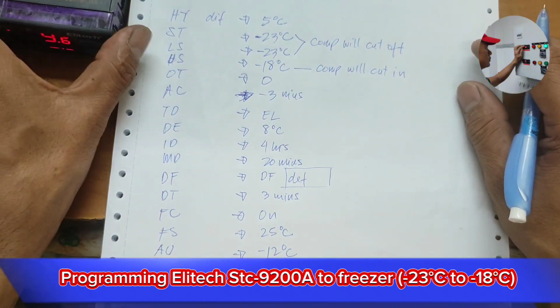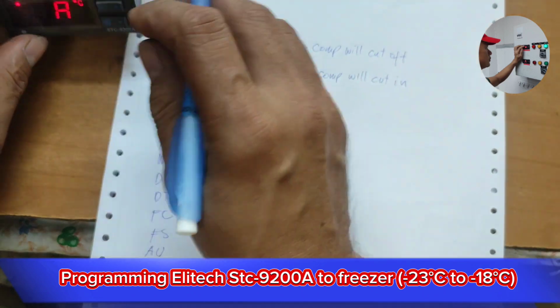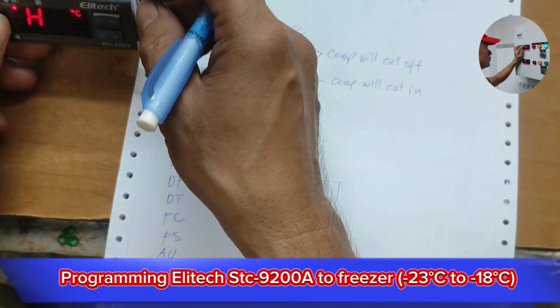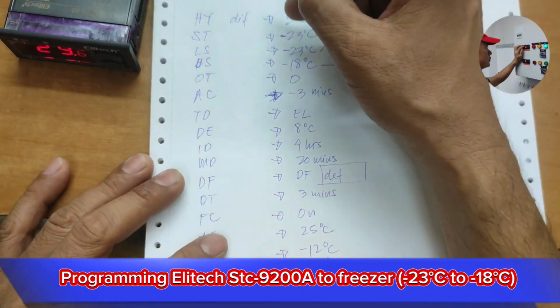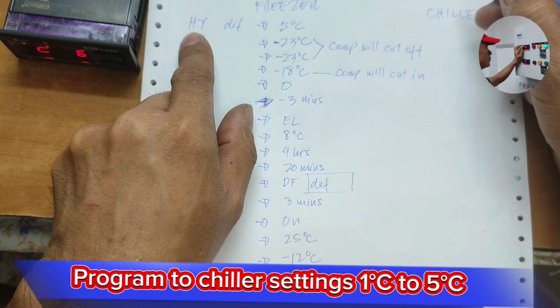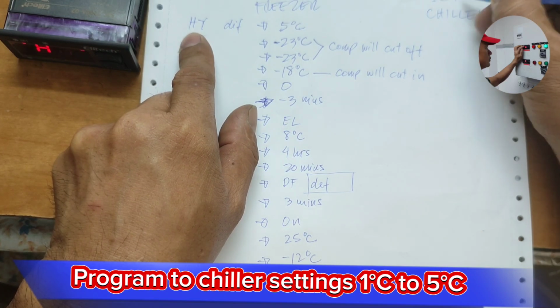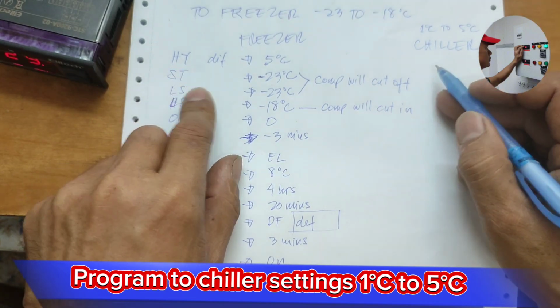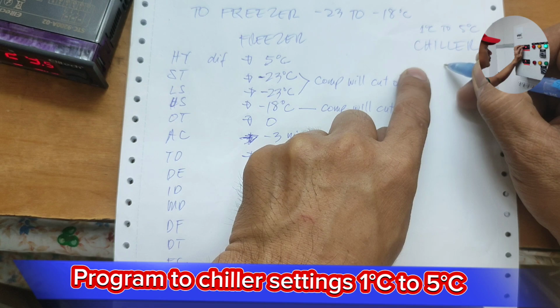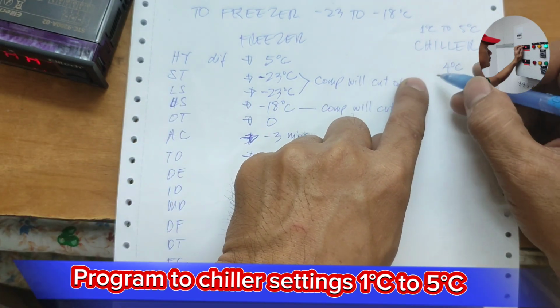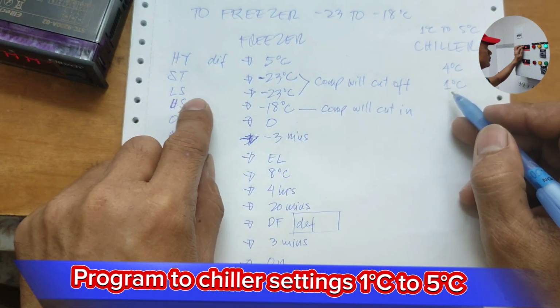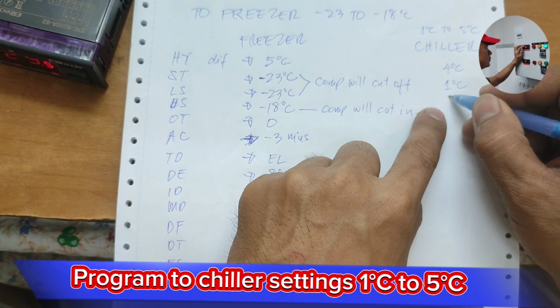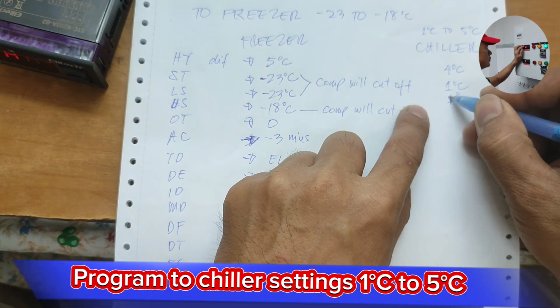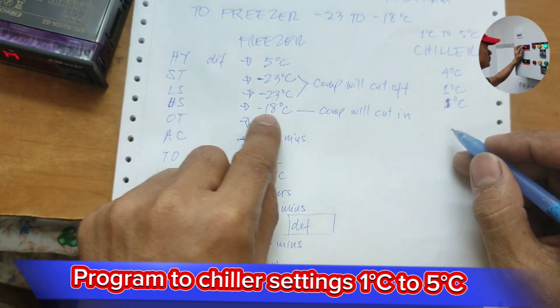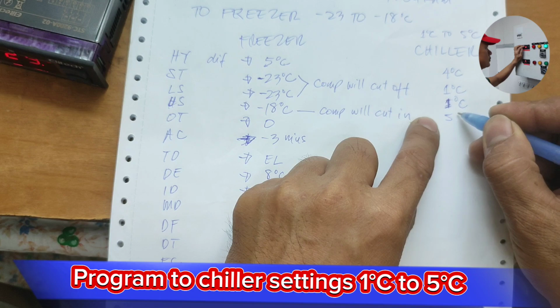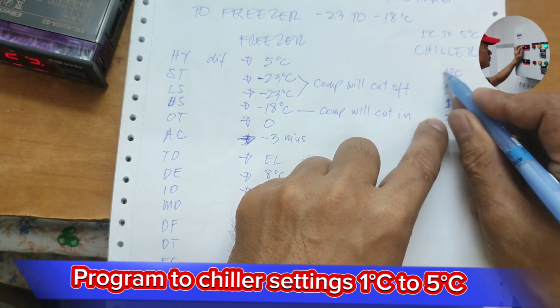If you want to program this into a chiller, now we have an HA alarm, because the sensor is not sensing any coolness. This is for the freezer. For the chiller, we have a standard temperature of 1°C to 5°C. This is our standard. For the HY, 0 to 4°C, and for the ST, set the set point to 1°C, and for the lowest set point, same, 1°C, and for the highest set point, set that to 5°C. 5 minus 1 is 4, so this is our differential.